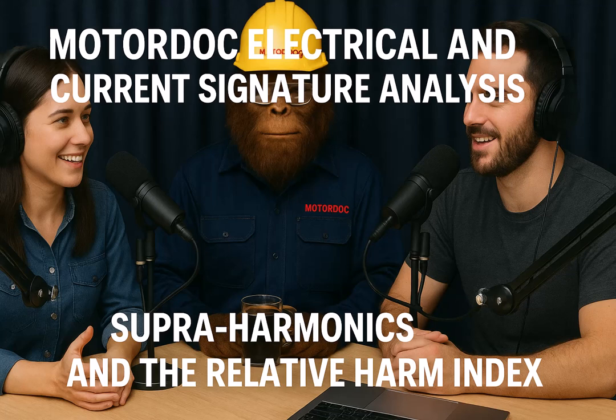Okay, so pulling it all together, what are the main takeaways for anyone maintaining rotating machines, maybe not just wind turbines? Well, the research strongly suggests MCSA is really effective for several common problems. Turn shorts: look for winding stress signatures, maybe stator defects appearing later. Right. Insulation to ground degradation: watch for those line frequency plus or minus 15 hertz sidebands, stator frequencies, and maybe that mirrored spectrum on the ground conductor. Sure. And general winding breakdown, especially with contamination or ground issues, often a combo: the plus or minus 15 hertz winding stress, stator defects, and the mirrored ground current spectrum.